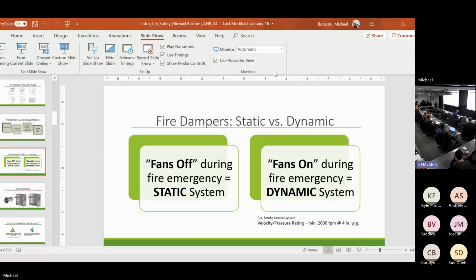That's my static. So we understand that concept, static versus dynamic is very important. One thing that I dislike, but it is true, you can use a dynamic damper in a static system. You cannot use a static damper in a dynamic system. That does not mean every damper from today forward is now going to be dynamic. There's a trade-off. It's a lot harder to pass tests dynamically.